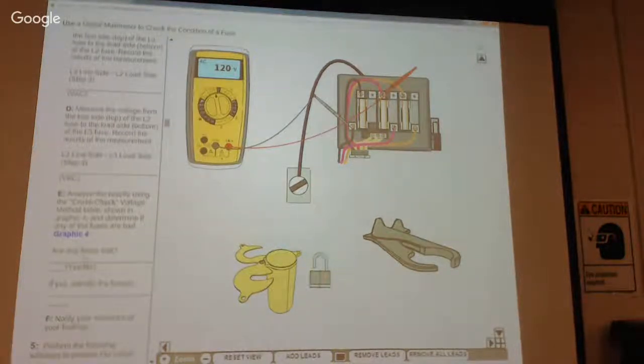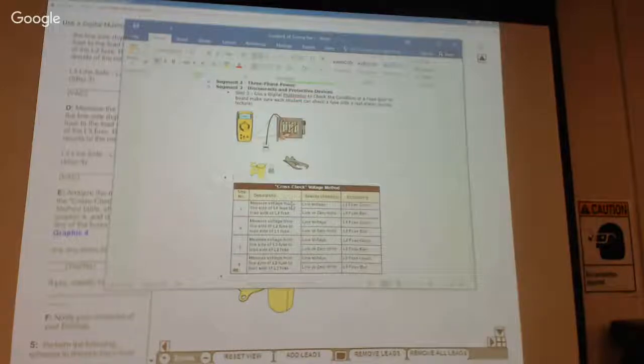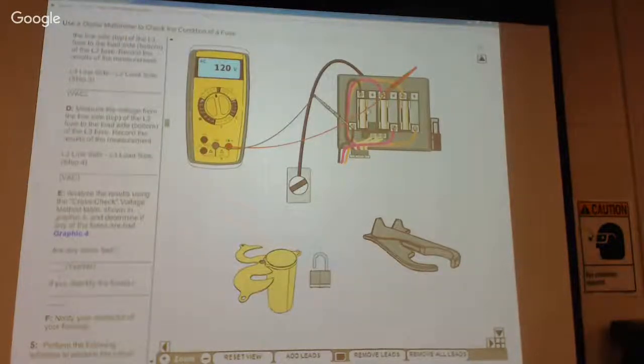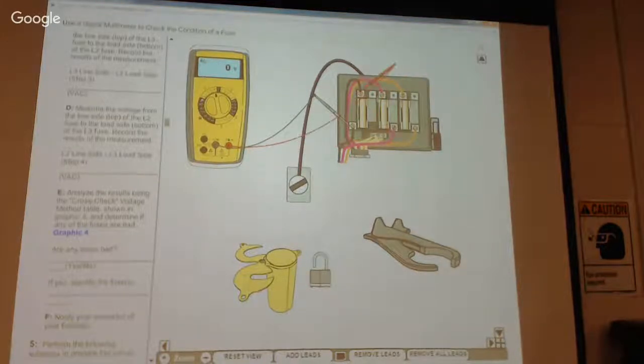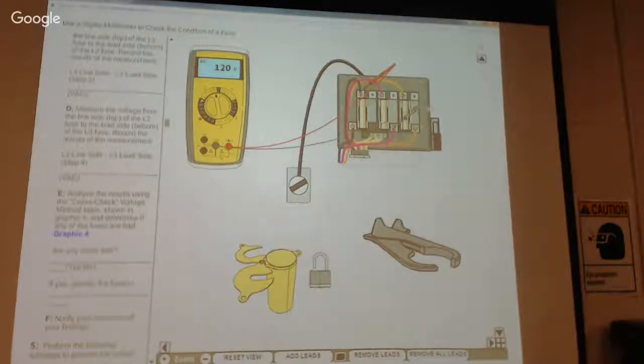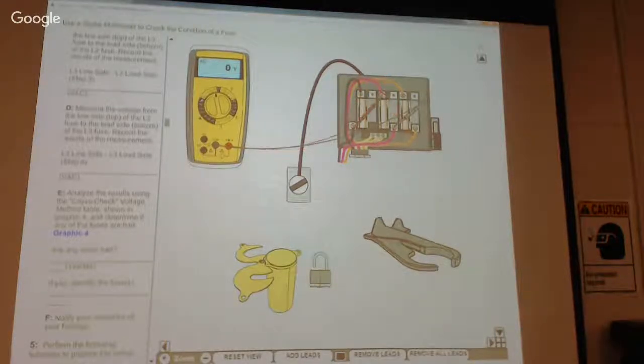We're going to do the cross check. They talk about the cross check method, which is right here. So this is what they want you to do. Measure voltage from line side of L1 to load side of L2 fuse. The load side is on the bottom. Electricity comes in the top and always goes out the bottom of these devices. And then it says measure voltage from the line side of L2 fuse to the load side of L1 fuse. It's got a little chart here that I'm going by. You can print it out.